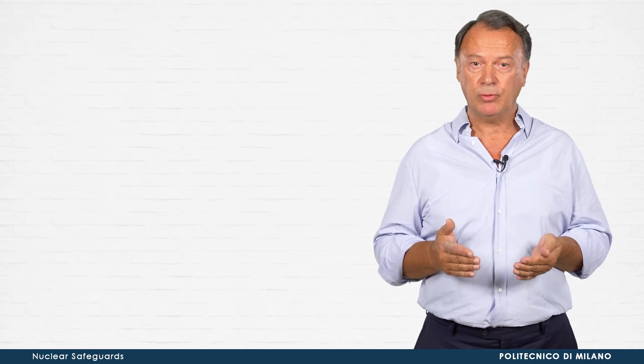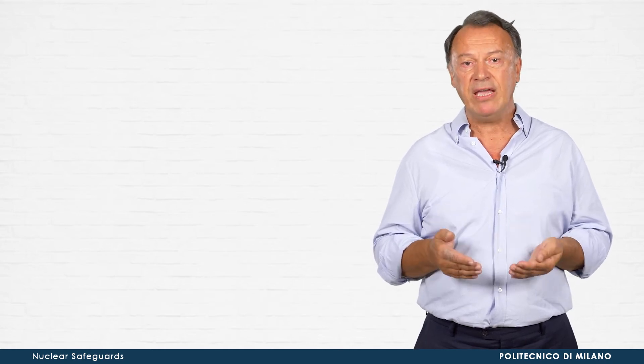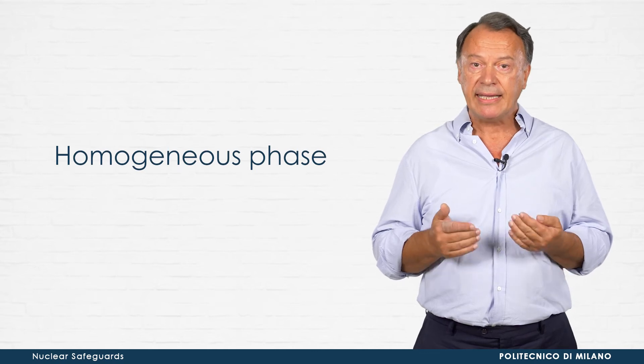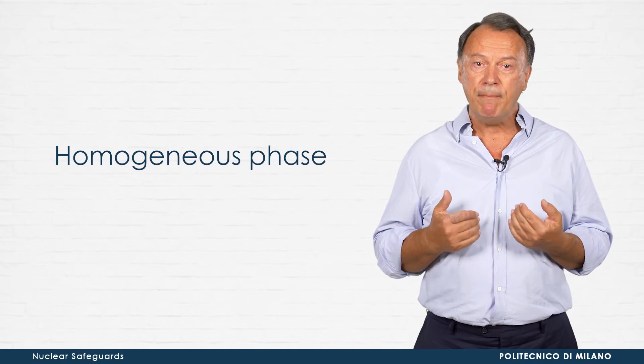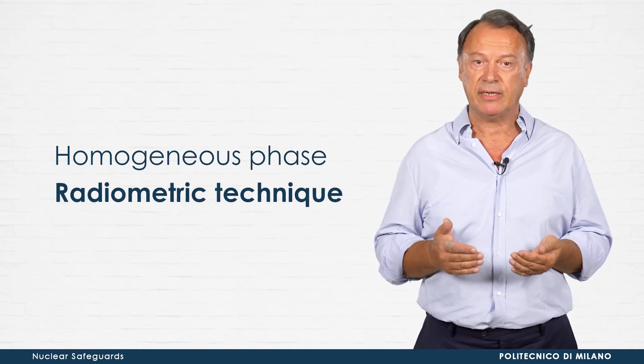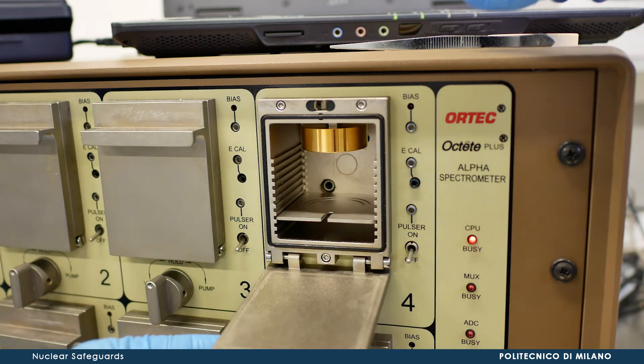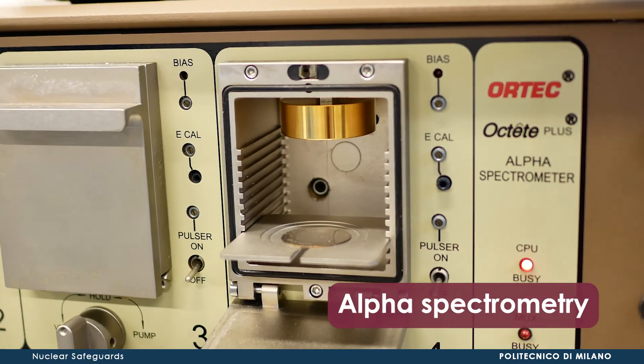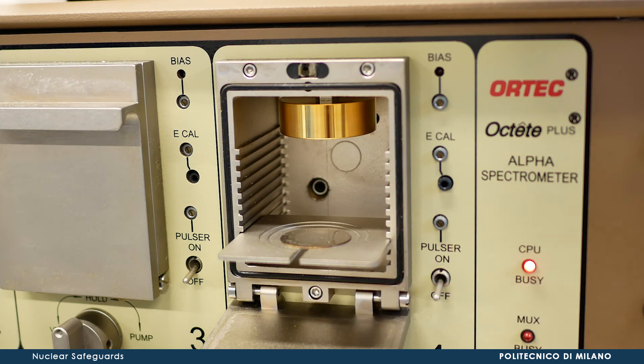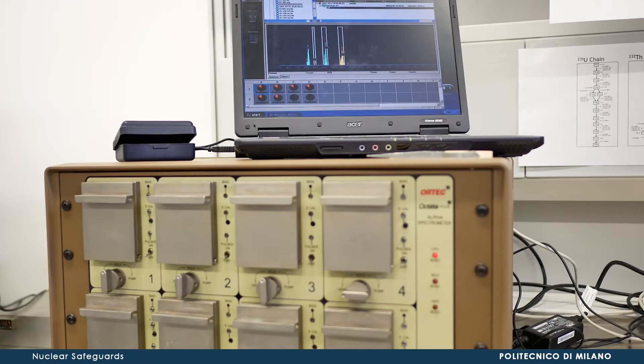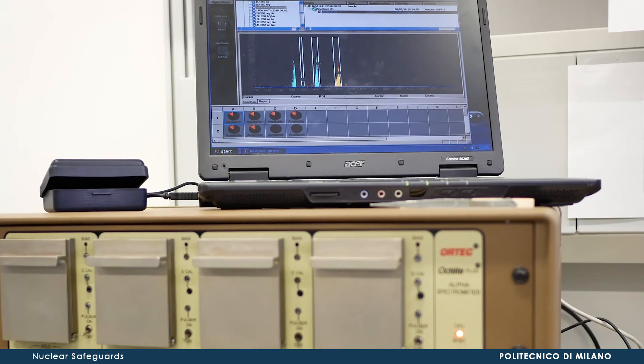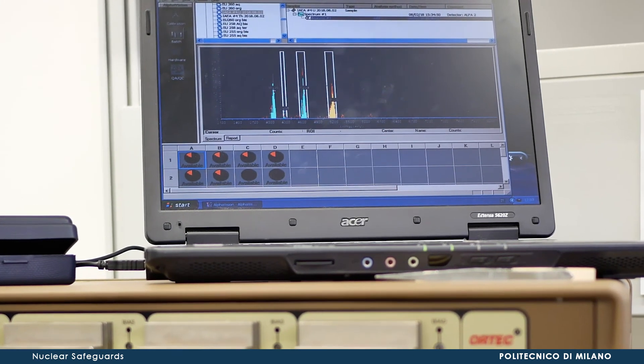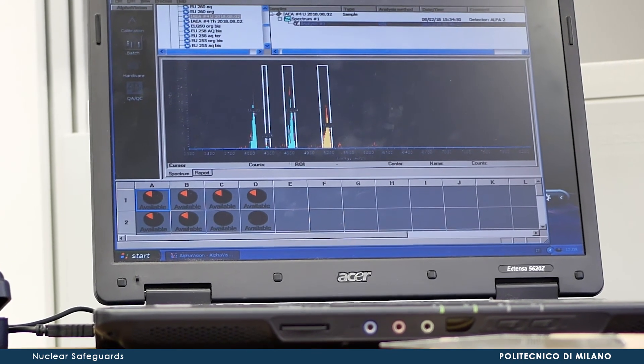Once the target radionuclide has been separated and is available in a homogeneous phase, the counting source has to be properly prepared to be measured by the most suitable radiometric technique. If the target radionuclide is an alpha emitter, the radiometric technique of choice is alpha spectrometry. The sample solution undergoes an electro-deposition process that produces a thin coherent coating on a stainless steel planchette, so that alpha particles are not self-absorbed and can be detected by a semiconductor detector under vacuum conditions.